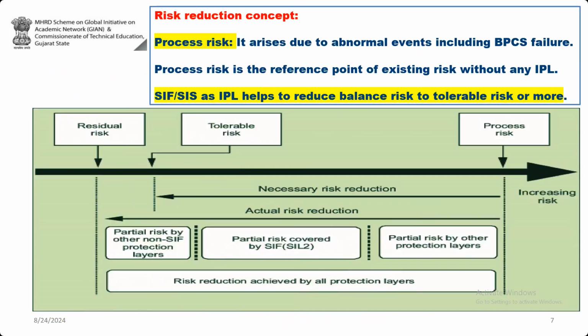Next. Whatever we have defined, this slide indicates very pictorially the same thing. Process risk is at this level. Now, this risk includes the risk of BPCS failure also, like I have written here, abnormal events including BPCS failure. From this risk, this is the level of your tolerable risk, which we discussed. Now, if you want to go from process risk to this risk, how can you go? You can go by protection layers. SIS or SIF is one of the protection layers, but there are other protection layers which will follow in the slides, which can reduce your process risk to even below the tolerable risk. So these risks are reduced by the layers of protection.